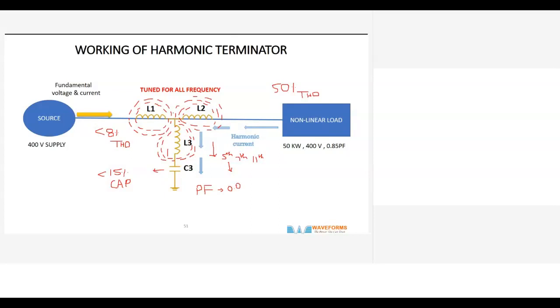So the power factor also improves to almost above 0.95, very surely above 0.95. It could be 0.98 depending on the size of the capacitor and the load. The power factor also improves. So you reduce all the harmonics, but normally drives only have fifth harmonic. So we design it from fifth to even the 100th harmonic. It can filter all the harmonics, and it will comply to IEEE 519 2018 2014, which is below 8% THD.